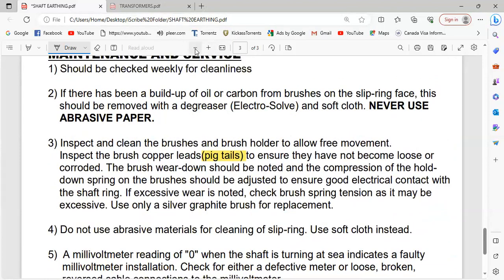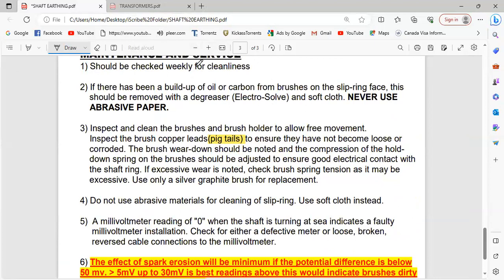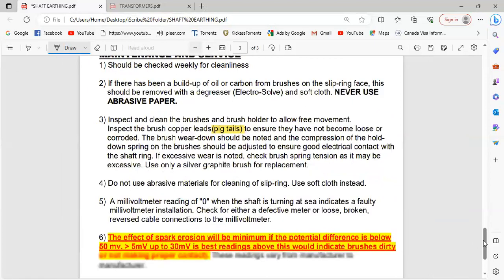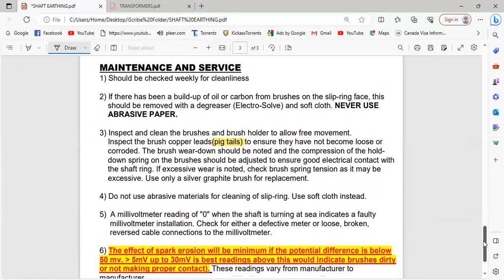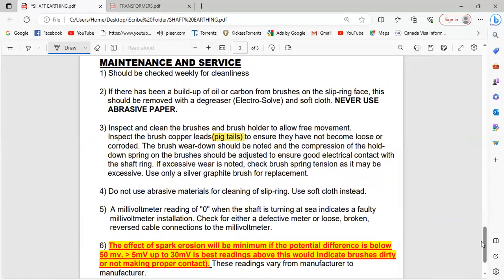So let me zoom out a bit so you can see all the maintenance. You can take a screenshot of this. Number 5, a millivolt reading of 0 when the shaft is turning out at sea. Now, if your shaft earthing is working properly, you will get some reading, right? And as I said, suppose this is your shaft meter.